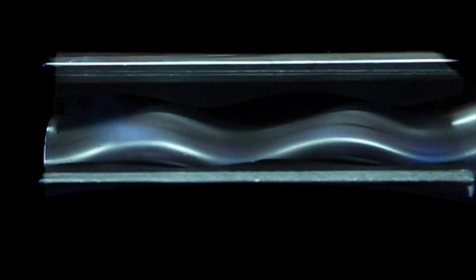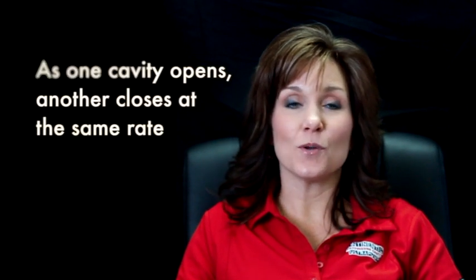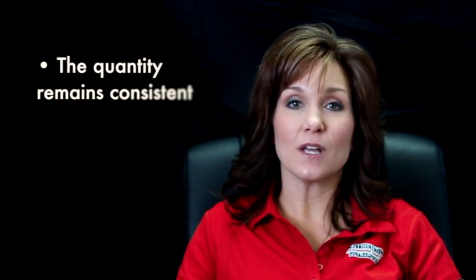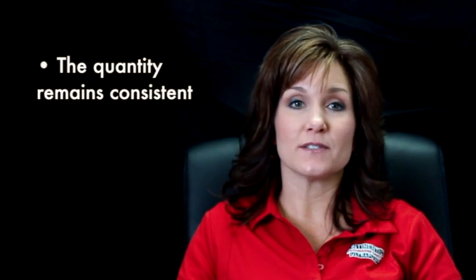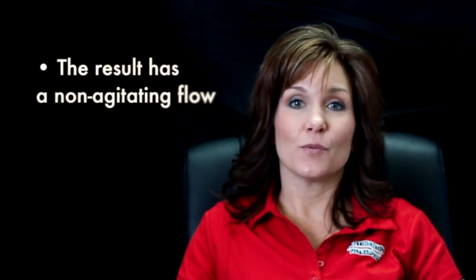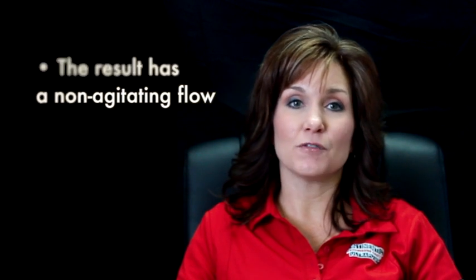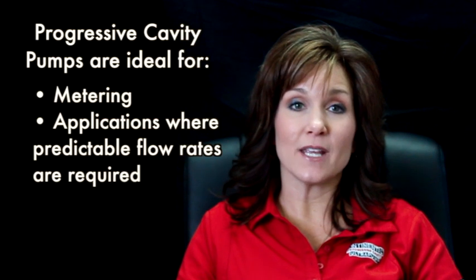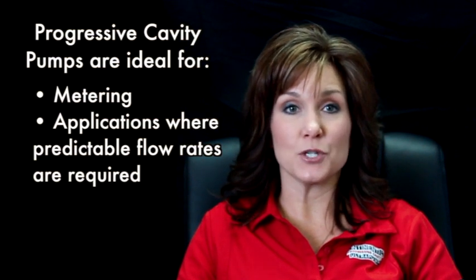The combination of the rotating rotor and the core of the stator results in a series of sealed cavities that progress from the inlet to the outlet, either due to pressure or gravity. As one cavity is opening, another is closing at the same rate, so the quantity going through both discharge and suction is continuous. The result is a non-agitating flow without the use of valves. This makes progressive cavity ideal for metering or other applications where predictable flow rates are required.